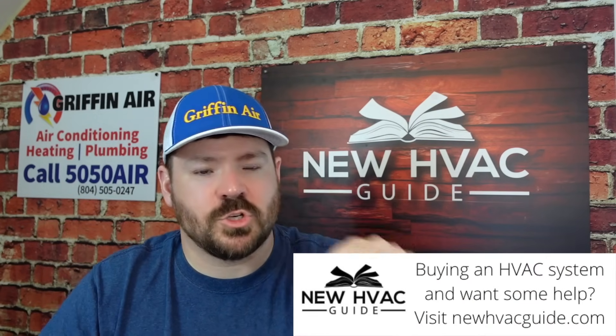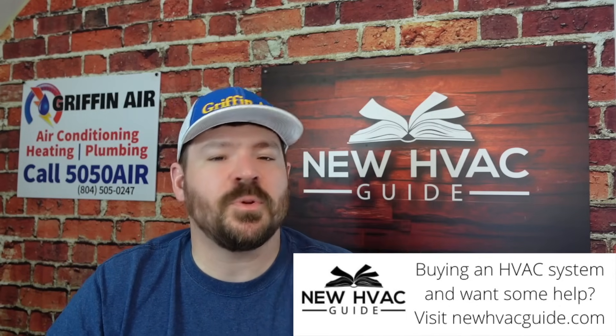First, I want to go through how residential systems work, because they do not operate like some systems — say like your car. With your car, you can turn it all the way up and it will blow cold, or back it down and not blow quite so cold. But with a heating and air system, instead of adjusting the intensity, your system runs at a fixed rate. If you set it at 72, typical residential systems at best run around a 20-degree delta T — meaning air goes in the return at one temperature and blows out 20 degrees cooler.